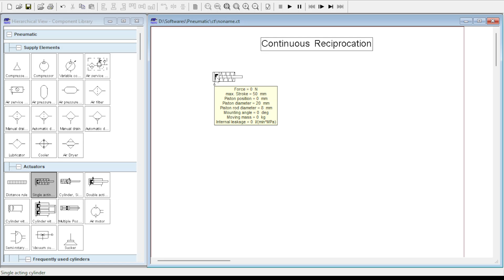Similarly, once the cylinder has completely extended, there needs to be a sensor which senses the complete extension of this cylinder. And hence, the continuous reciprocation circuit of this cylinder will basically rely on the operation of two sensors, which can either be limit switches or some roller or mechanically actuated DCVs that can help in sensing the extremes of piston strokes. Say the extended stroke of the cylinder or the retracted stroke of the cylinder are to be sensed by the limit switches.